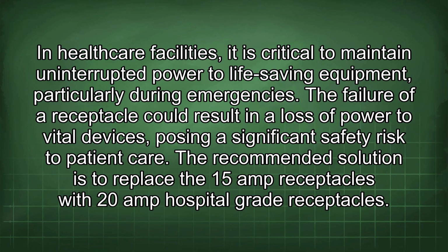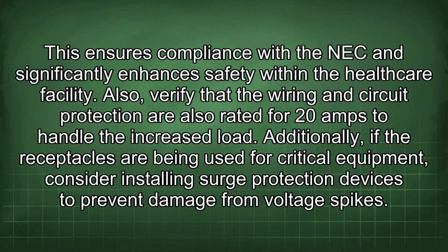to patient care. The recommended solution is to replace the 15-amp receptacles with 20-amp hospital-grade receptacles. This ensures compliance with the NEC and significantly enhances safety within the healthcare facility. Also, verify that the wiring and circuit protection are also rated for 20 amps to handle the increased load.